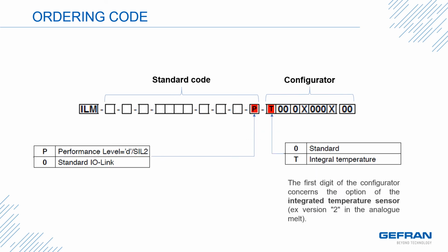The last block in the standard code allows you to select either the standard I/O link or with Performance Level D in SIL2. The first block in the extension or the configurator allows you to select with or without the integral temperature included.